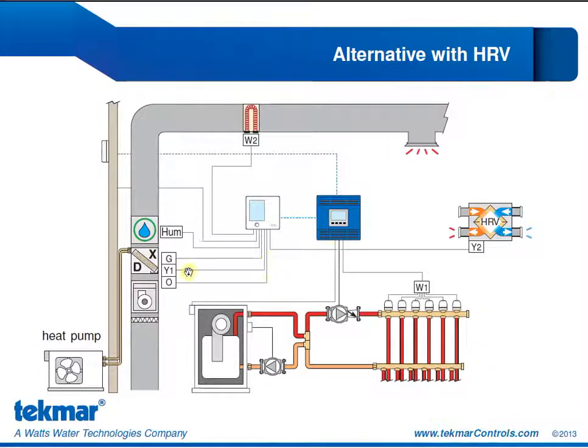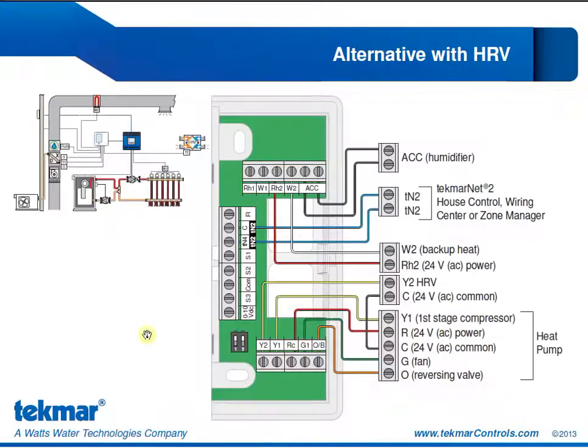Here is an alternative with an HRV. Similar to the application we just saw, we have a first stage of heat from the radiant floor, a second stage of heat at the heat pump controlled with the Y1 relay, and a third stage of heat, the electric strip backup, controlled with the W2 relay. Notice here it's a single stage heat pump. We're restricted to using a single stage heat pump because our Y2 relay will be controlling the HRV. When we're in cooling mode, we have one stage of cooling from the heat pump, and we are showing the humidifier in the ductwork.